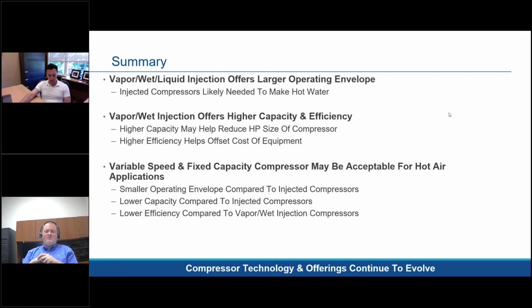And one more benefit, I guess, to the vapor and wet injection, other than just the extended envelope, is that the increased efficiency and increased capacity help offset some of the cost of the extra solenoid valve, extra heat exchanger, expansion valve, and the piping to go back to the compressor, because you can use smaller compressors to get more capacity due to that injection into the compressor itself and the increased mass flow.